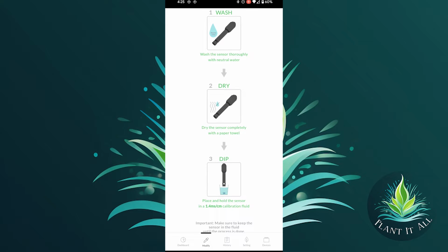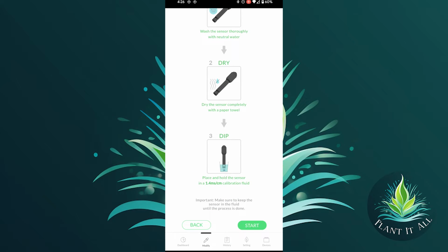One really important note here, when you dip the probe into the solution, make sure you give it a little bit of a jiggle around in the solution. This is going to help make sure that there's no bubbles on the sensor. And if there's air bubbles on the sensor, it actually could prevent it from reading properly. So get it into the solution, swish it around a little bit, nothing crazy. We are just making sure there's no air pockets on there. And then you can go ahead and hit start.